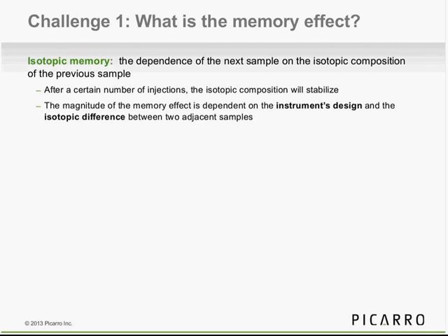It is dependent on the instrument design. Sorry, the ways to deal with it are not dependent on the instrument design. The size of the memory effect is often dependent on the instrument design. It's also dependent on the isotopic difference between two adjacent samples. The larger the difference, the more the memory effect you'll notice.